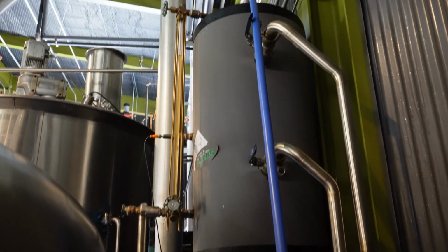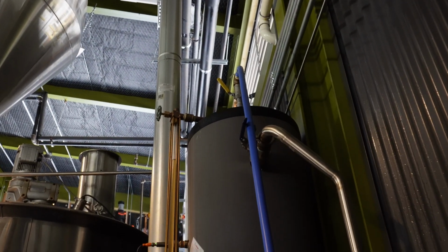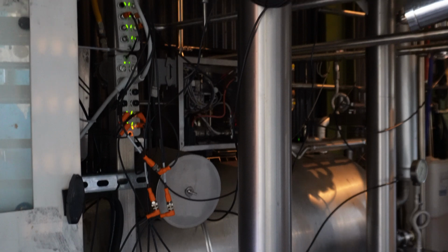So Matt and Kirby wanted to implement a thermal fluid heater as the solution. Basically, instead of having steam pumped through jackets on tanks, they're heating up an oil, a food grade oil, to hot temperatures that then pumps through those jackets, transfers heat to the liquid, specifically wort in this situation. And that is the same theory, same process as how steam is generated, but it's not steam, it's just oil. So the components are, there's a reservoir that holds the excess oil outside of the oil that's in all of the pipes in the jackets, because you need to purge all of that so there's no air in the system. That runs through a heat exchanger in this big burner unit where a large direct fire flame is heating up.